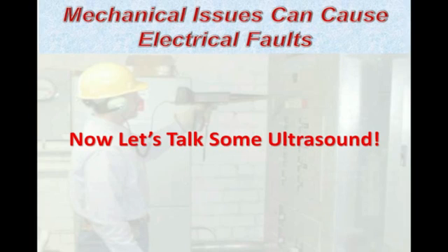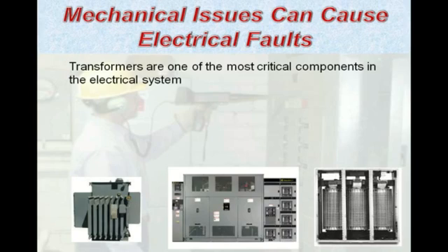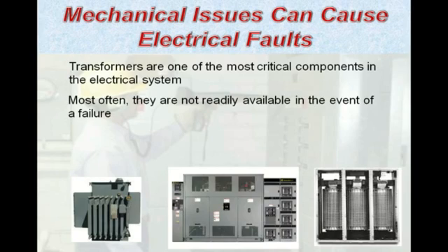I'm going to focus today on a singular component within the electrical system, a transformer. And we all know that this is probably one of the most critical components in the electrical system. Large or small, there are many other items and systems and operations that could and would be affected by the failure of a transformer. Most often, they are not readily available in the event that it fails. As time has gone by, the availability of transformers as far as replacements and their lead time has exponentially increased. And that's getting tighter and tighter for a number of various reasons as time goes by.